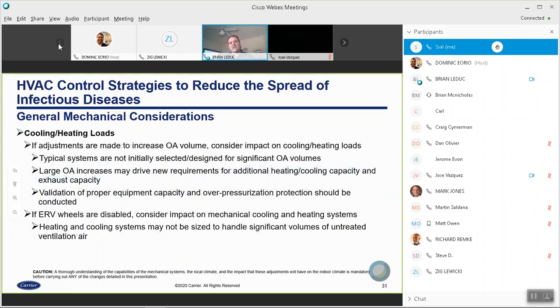Again, if you're going to make adjustments to your outside air intake, you have to consider that impact on your cooling and heating loads. Your systems are not typically sized for significant amounts of outside air. If you choose to do so, you might have to make some changes to the equipment to increase its capacity, which obviously is not something that can be done easily. If you're increasing your airflow, be cognizant of how that's affecting the pressurization in the building. As I mentioned, ERVs can be disabled, but the equipment guys flag that if you disable an ERV, and the ERV took a considerable amount of the load, you've got to be aware that that's going to go away and make sure the remaining capacity of the equipment can deal with the volumes of untreated air.